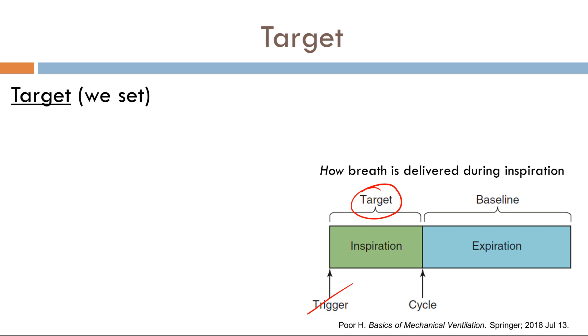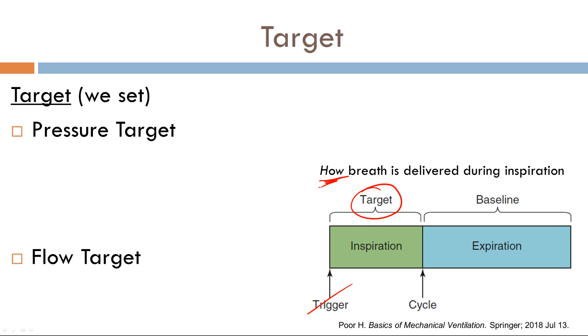What is target? Target is how a breath is delivered during inspiration — is it delivered fast or is it delivered slow? The target variable is delivered in one of two ways: you can either have a pressure target or a flow target. You cannot have a volume target because volume doesn't designate how a breath is delivered. Volume over time is flow, so technically you cannot have a volume-targeted mode.